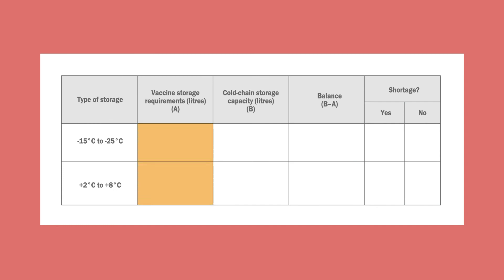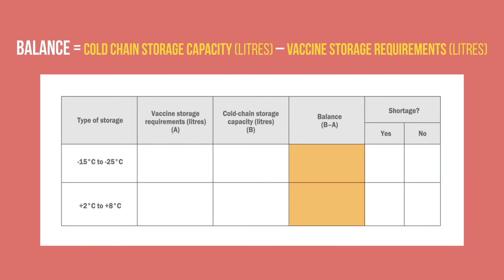When you know your vaccine storage requirements and cold chain storage capacity, you can determine if you have sufficient cold chain storage capacity to store the vaccines. List your vaccine storage requirements and cold chain storage capacity for both temperature ranges. For each type of storage, subtract the required vaccine storage from your available cold chain capacity. If the result is a negative number, you have a shortage issue that will need to be addressed. For example, if you had 528 liters of refrigerator and cold room space available but need 600 liters for an incoming vaccine shipment, subtracting 600 from 528 gives a negative number, meaning you will need to find additional cold chain storage space to safely store all your vaccines.